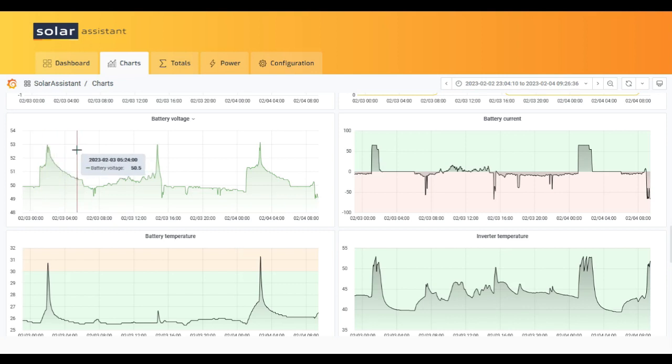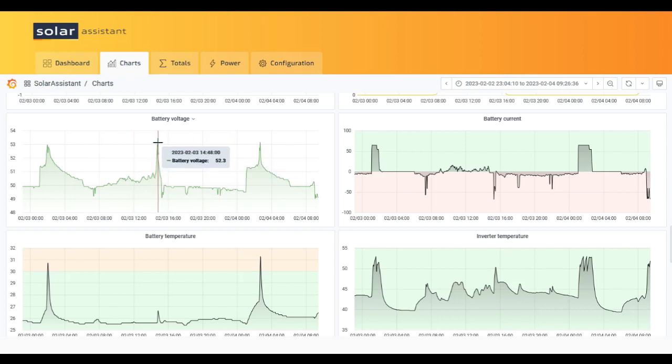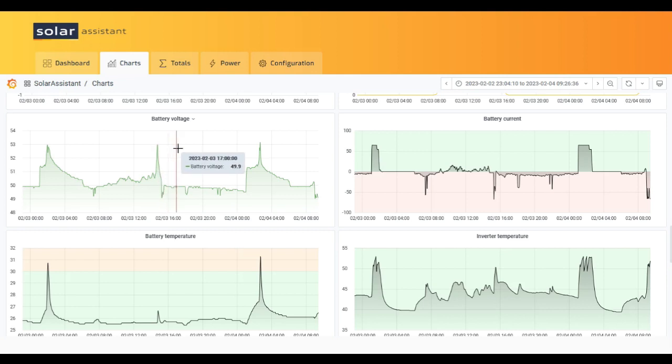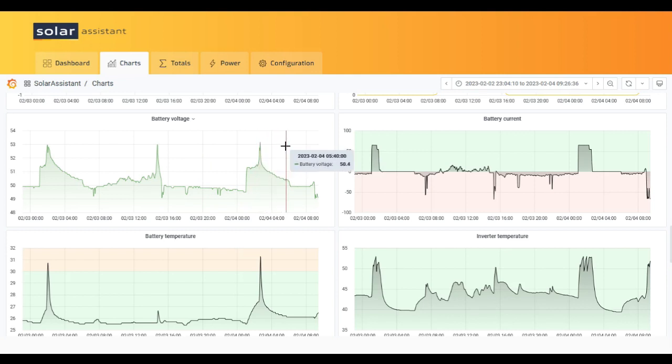Again here we can see going up to 53 point something and then steadily slowly dropping down to float voltage. The same here, load, load, load and then steadily dropping to float voltage.